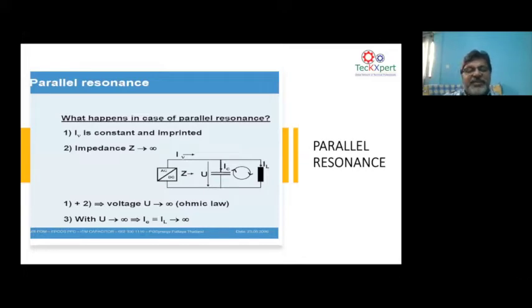which is basically a DC rectification and AC inversion. That is why AC-DC is shown like that. And now it is a harmonic source. You can see this harmonic source is producing harmonic currents. Now the entire impedance of the network, the inductive impedance, that is the transformer impedance and the source impedance of your BESCOM network, in parallel with your capacitor bank, your APFC panel, maybe the capacitor bank installed in your facility, when they work in parallel, you can see how the equation looks. The effective impedance of the parallel network is Z1 Z2 divided by Z1 plus Z2. That is how the effective impedance is calculated.